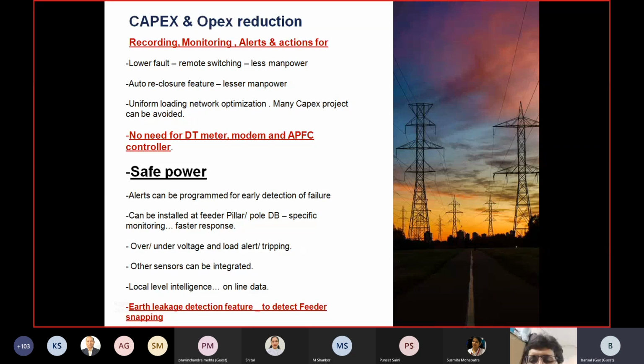So we normally try to maintain it below 70%. That means at peak, the transformer loading should not be more than 70% of the transformer capacity. But there are incidents when it used to go 80%, 90%, sometimes even 100%, because suddenly a big load has come and it has crossed the value.